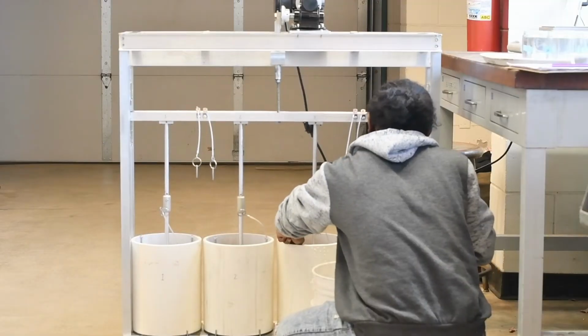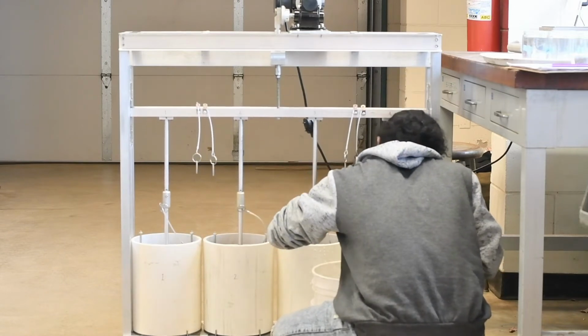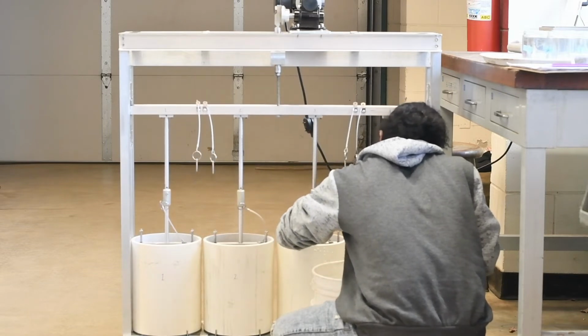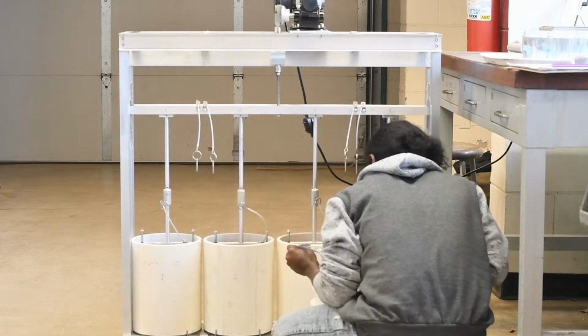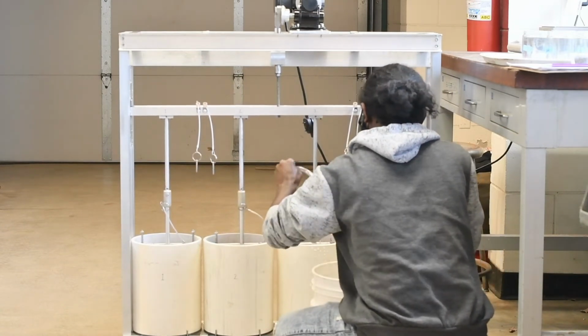Go ahead and test the machine for a minute or two to make sure the mesh of the top sieve does not break the surface of the water when running, and that the water on the outside of the sieve is moving in concert with the water inside the sieve. This means you've successfully evacuated any air bubbles that could compromise the assay.